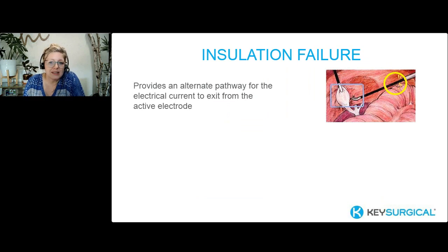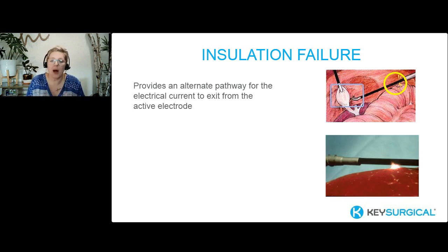The next thing we have is insulation failure, and not a funny story, but kind of funny, right? We take pride in things that we're able to do in our jobs, which is so awesome. But insulation, all of our active electrodes that conduct electricity are insulated in order to safely and precisely apply electrical current, right? So what happens with insulation failure, a break in that insulation where we have conduction going through, is it provides an alternate pathway for electrical current to exit from that active electrode.